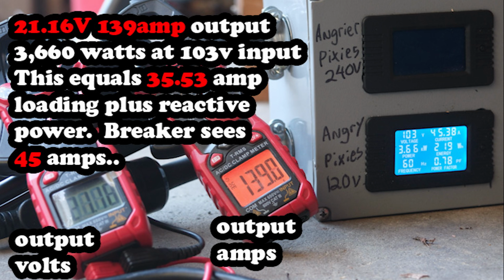That equals 35.53 amps of actual power consumption. And then, of course, because the power factor is relatively poor and it's spitting reactive power back out, the actual breaker loading that the breaker would see is 45 amps. So that's absolutely absurd. Good luck finding any generator that would handle that kind of a load on a 120 outlet without letting a breaker trip.